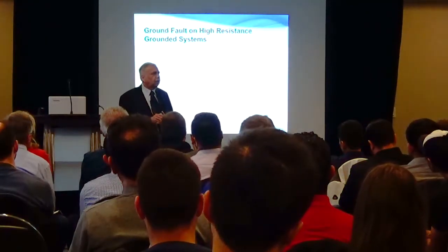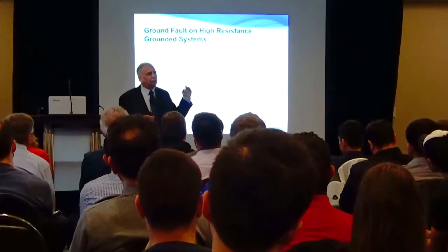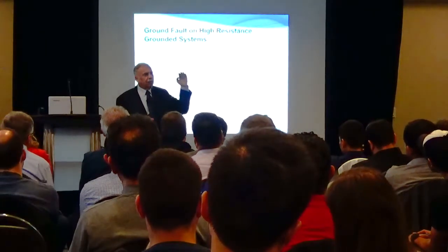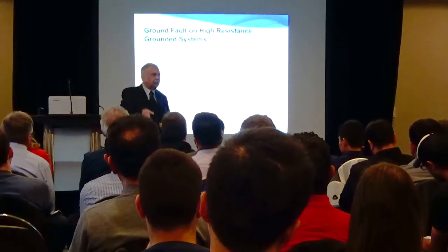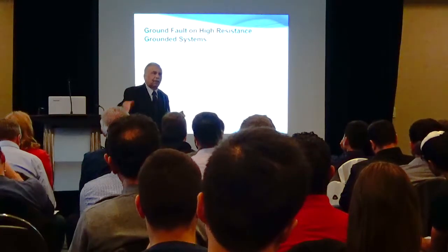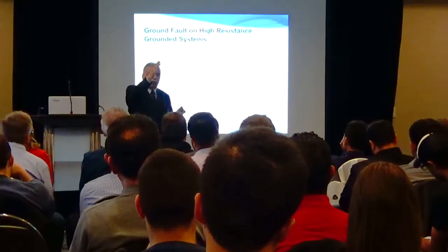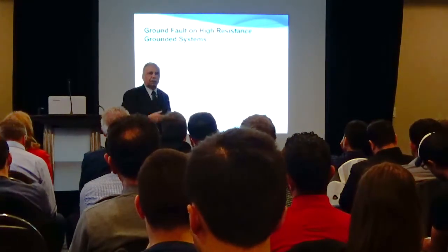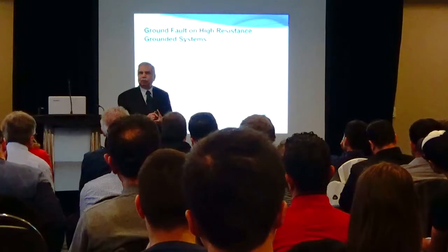The weakness in the insulation is now progressing. It takes a while for the insulation to grow from good insulation to bad insulation. It's not a screwdriver falling. It's a gradual degradation of the insulation. Eventually, it turns into a fault. So you have some time to respond. It's predictive. So this kind of information is very, very useful for predictive maintenance.